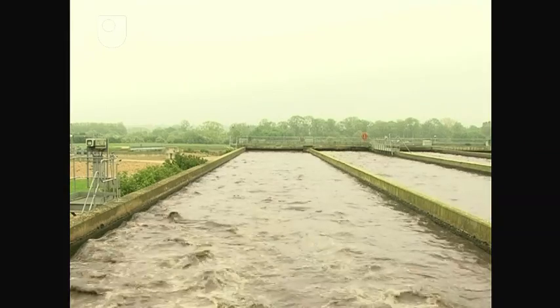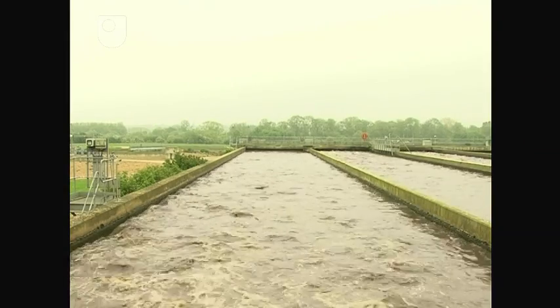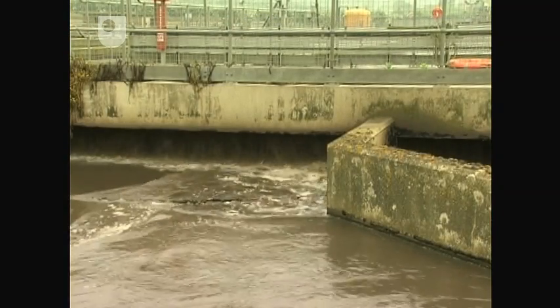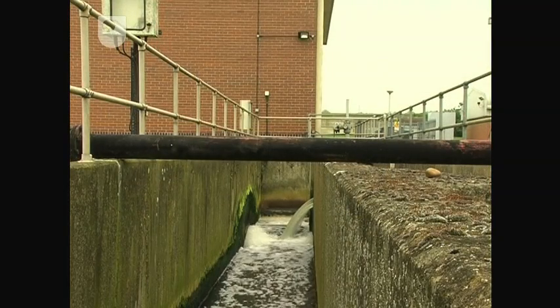The remaining system is the oxygen ditch, where almost one-fifth of the sewage at this plant is treated. Interestingly, the oxygen ditch doesn't require primary settlement. The sewage is aerated with the help of large brush aerators and the effluent moves around the ditch, allowing the organic matter to be degraded by microbes in suspension. On exiting, it goes to a settlement tank and then to the gravel filter.